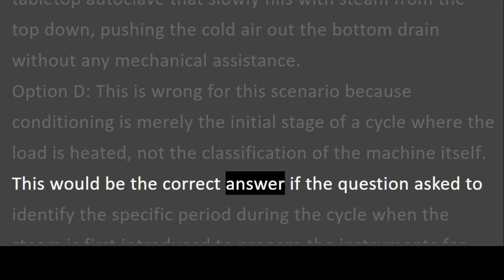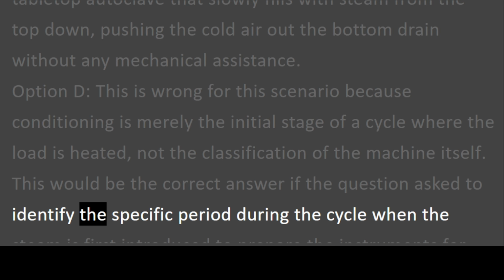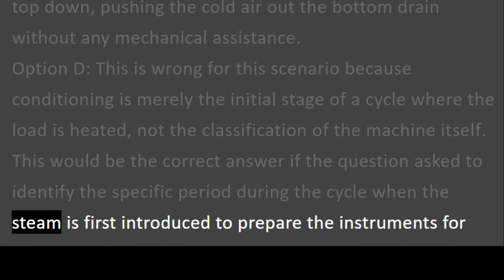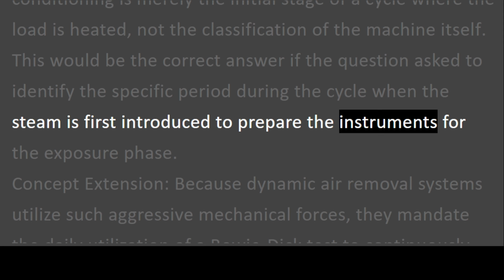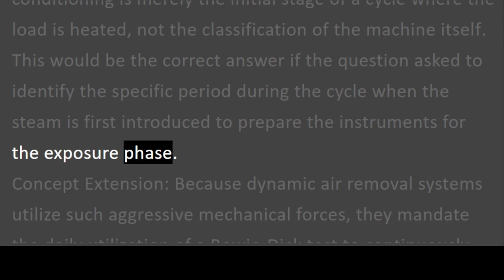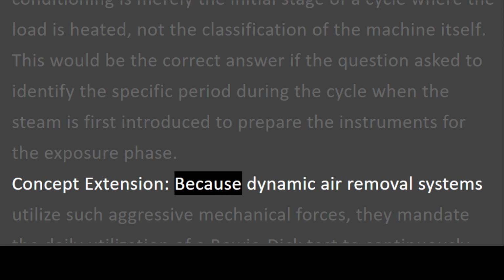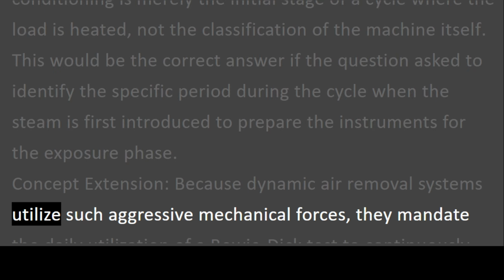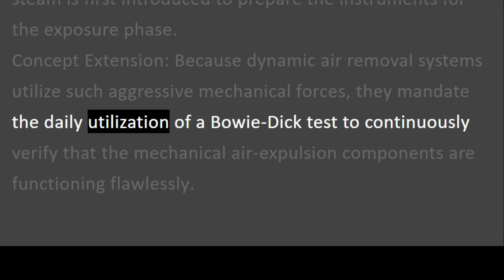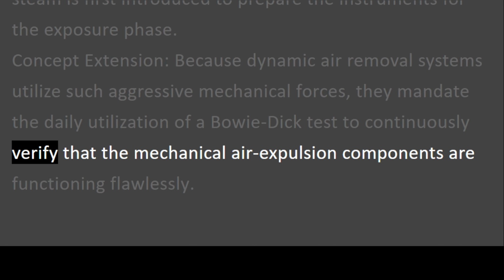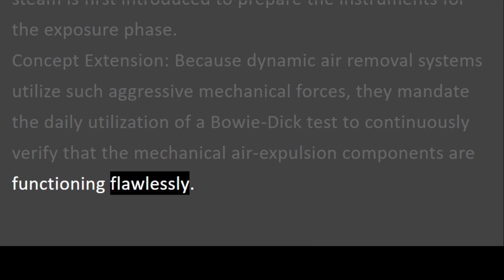This would be the correct answer if the question asked to identify the specific period during the cycle when the steam is first introduced to prepare the instruments for the exposure phase. Concept extension. Because dynamic air removal systems utilize such aggressive mechanical forces, they mandate the daily utilization of a Bowie-Dick test to continuously verify that the mechanical air expulsion components are functioning flawlessly.